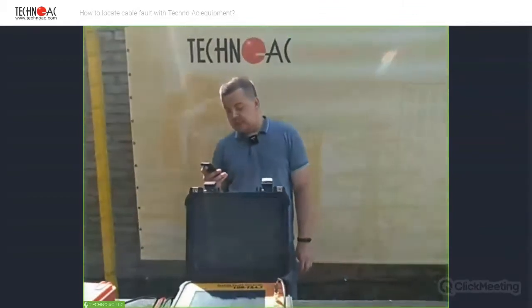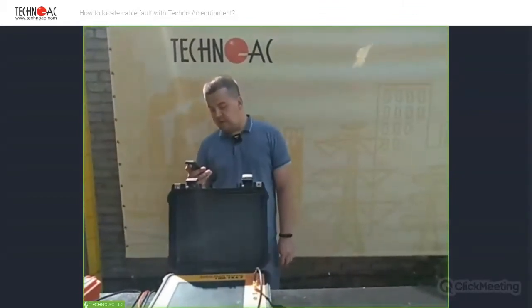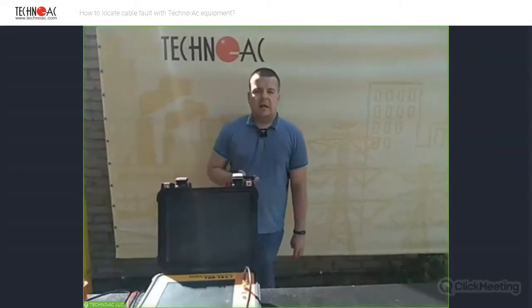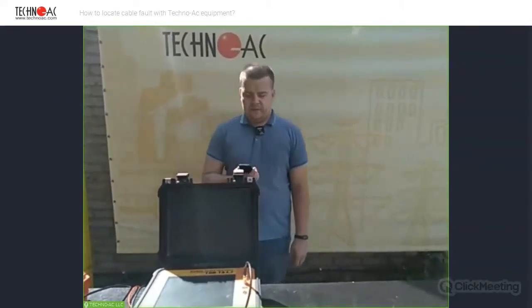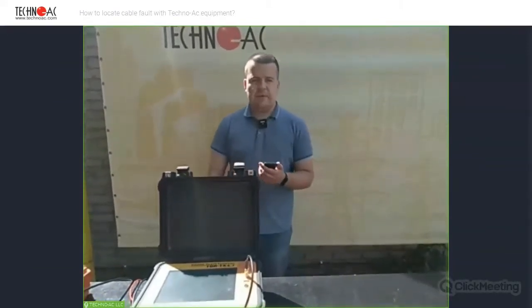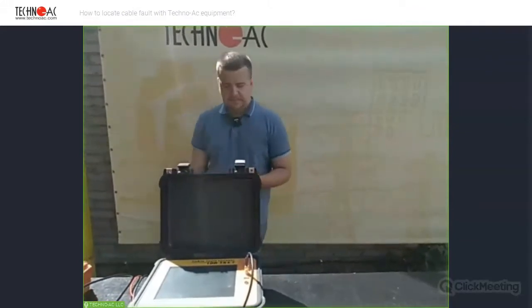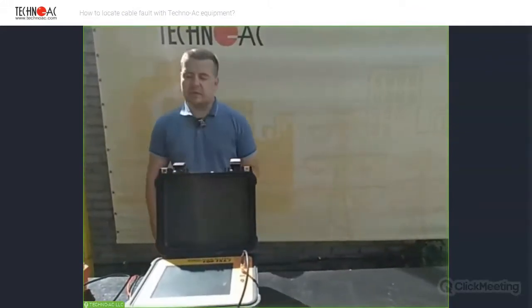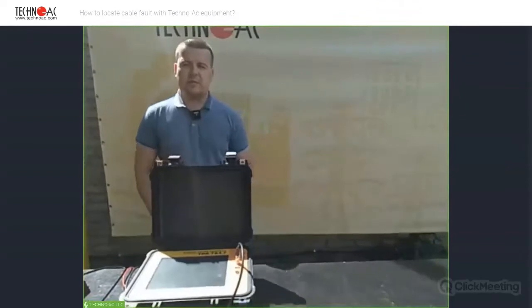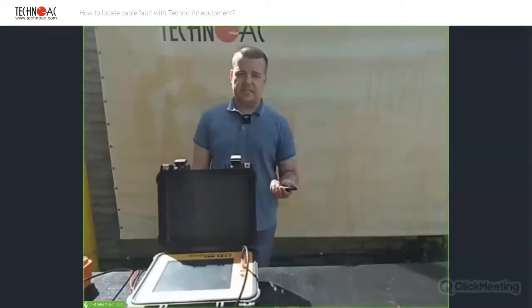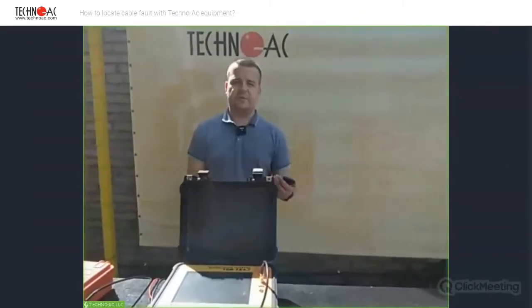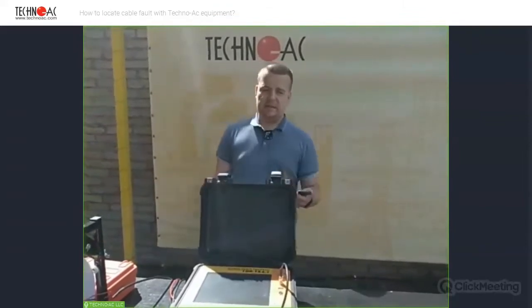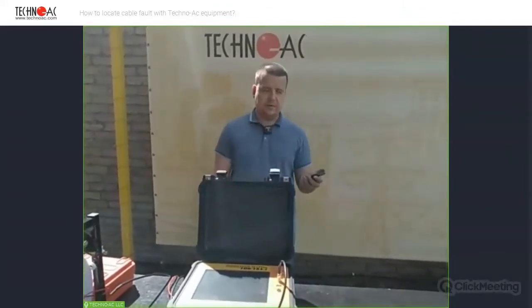What happens if the failed cable is shielded? Does TDR give a different result? The TDR will not have a different result, because generally you connect the cable to the conductor or to the shield. If you're testing the shield, you will get the fault of the shield. If you're testing the conductor, you will see the fault of the conductor.